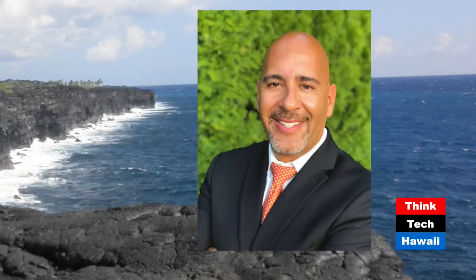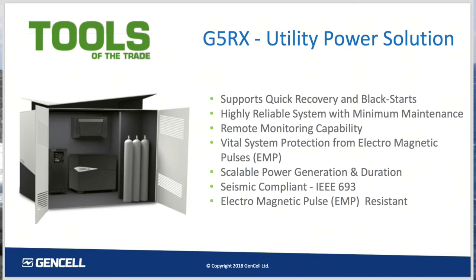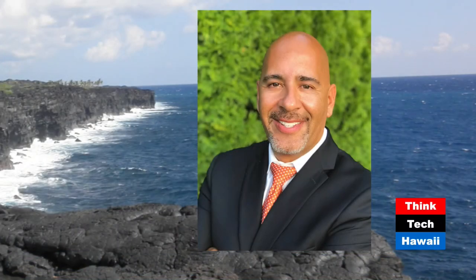So what this system does is extend the range of those batteries. You may still have those same battery banks for 8 hours, 12 hours, whatever it may be, but we also attach a charger that our fuel cell converts energy to supply, which then charges the batteries. Or we can eliminate the charger and just charge the batteries directly. The idea is that this extends the ability for that substation to have the power necessary to restore power so the transmission lines can provide power to the end user. This design was actually developed with the support and guidance of one of the largest companies out west, who helped us create a specific solution for their application.